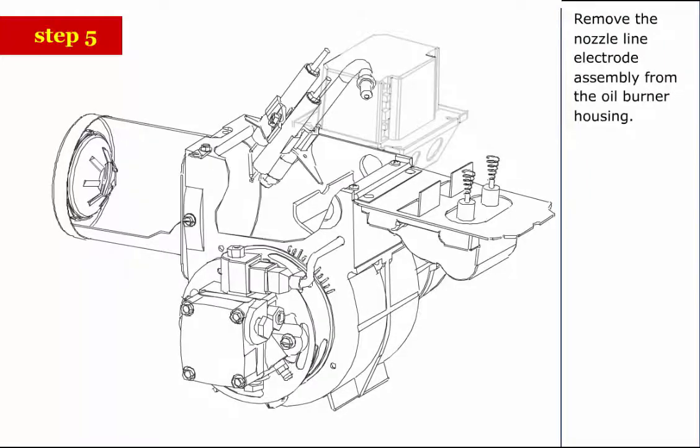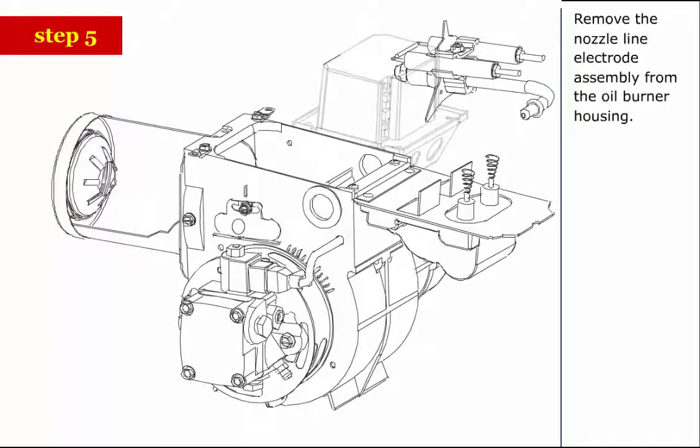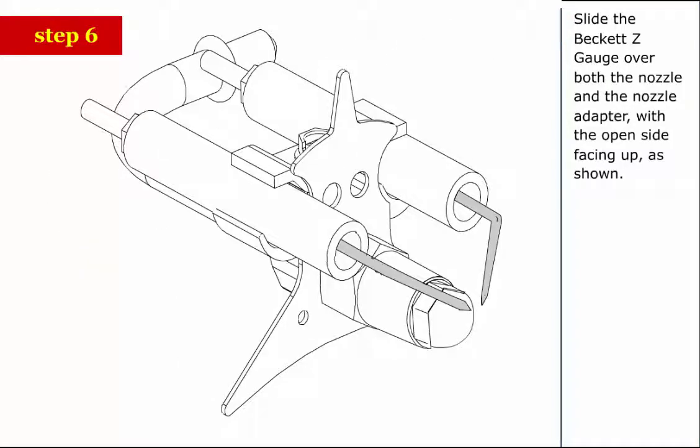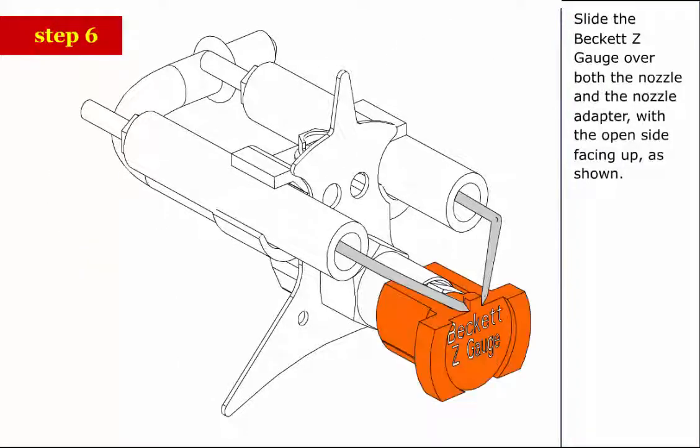Step 5: Remove the nozzle line electrode assembly from the oil burner housing. Step 6: Slide the Beckett Z gauge over both the nozzle and the nozzle adapter with the open side facing up as shown.